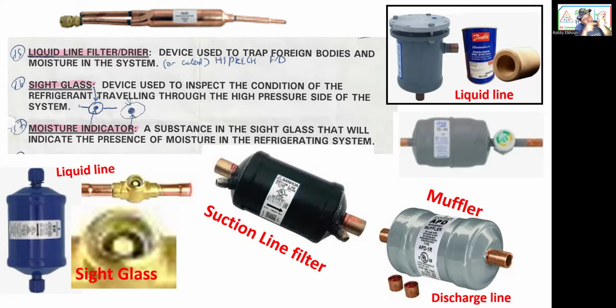Moisture indicator inside the sight glass. That's to tell us if there's moisture in the system or not. Right. But don't get confused with the muffler. It looks like the filter dryer, right? But it's not. It's a muffler. It says on it muffler, and it's on the discharge line. It's not on the liquid line, and it's just for noise.